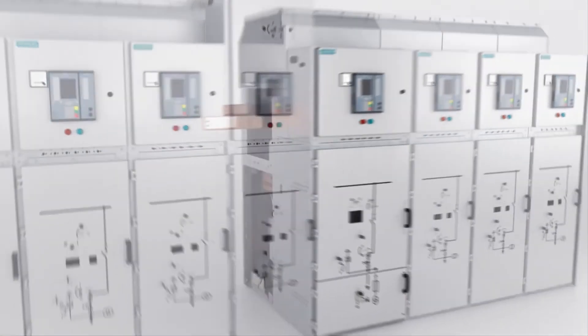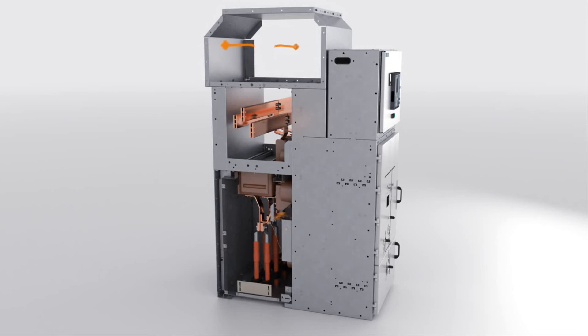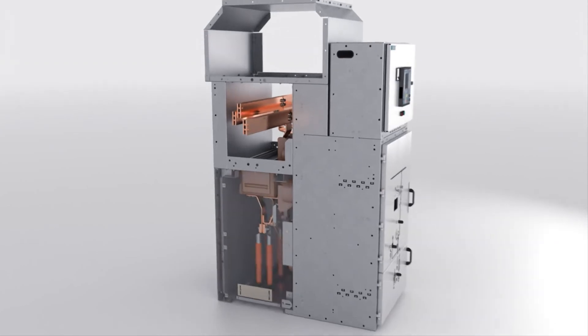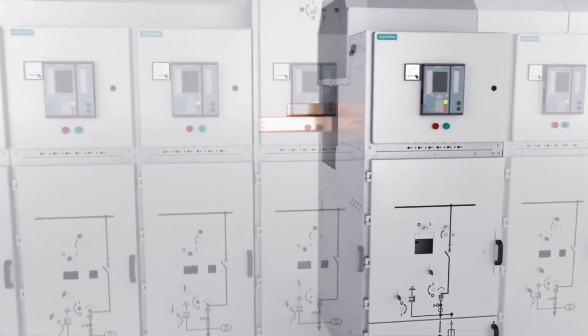The overpressure and the hot internal arc gases are relieved upwards separately from the individual compartments. They are discharged into the switchgear room through absorbers or outside through a pressure relief duct.